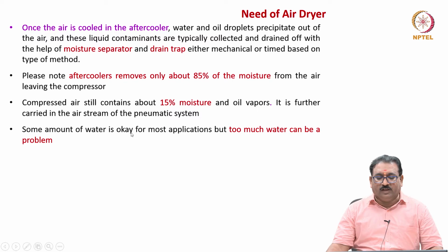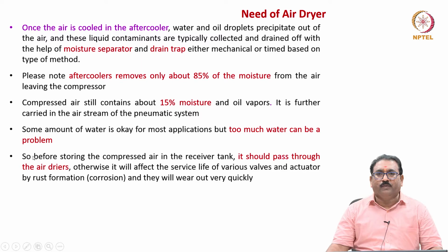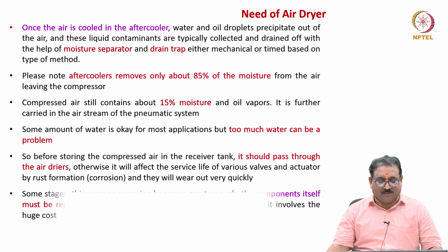Some amount of water is okay for most applications, but too much water can be a problem. So, before storing the compressed air in the receiver tank, it should pass through the air dryers. Otherwise, it will affect the service life of the various valves and actuators by rust formation. And hence they will wear out during their operations.